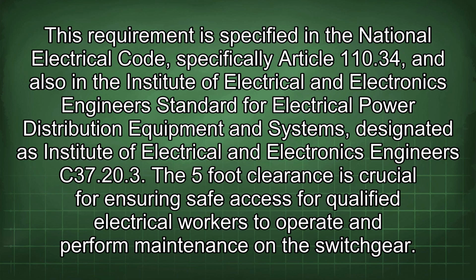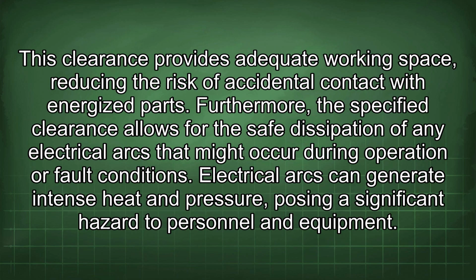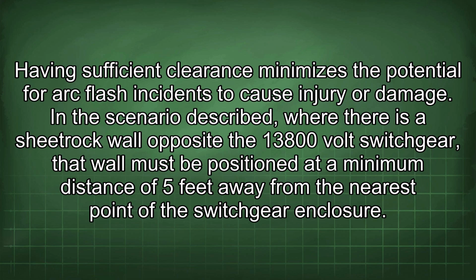the switchgear. This clearance provides adequate working space, reducing the risk of accidental contact with energized parts. Furthermore, the specified clearance allows for the safe dissipation of any electrical arcs that might occur during operation or fault conditions. Electrical arcs can generate intense heat and pressure, posing a significant hazard to personnel and equipment. Having sufficient clearance minimizes the potential for arc flash incidents to cause injury or damage.